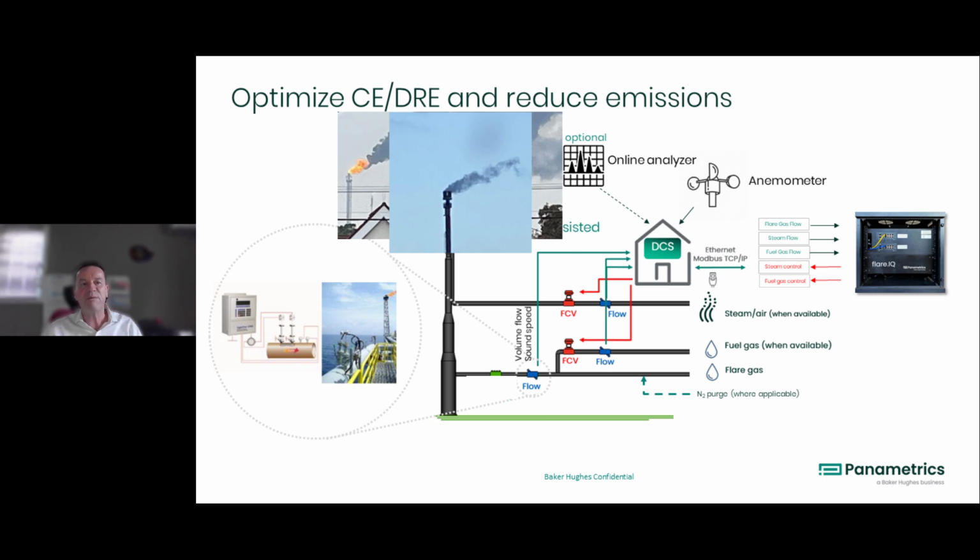But on kind of normal operations, it's also not infrequent to see these kinds of flares where it seems that the smoke, there's actually steam getting out of the flare tip, and you might still have a little bit of combustion, but in this instance, the combustion drops down to the likes of 60, maybe 50%, and then the methane slip becomes really big, even if the operator may still report a 98% efficiency, where if you see that, it is guaranteed that it is not.